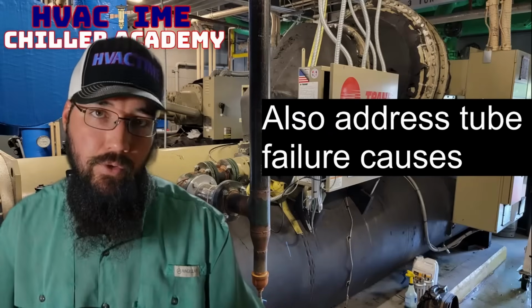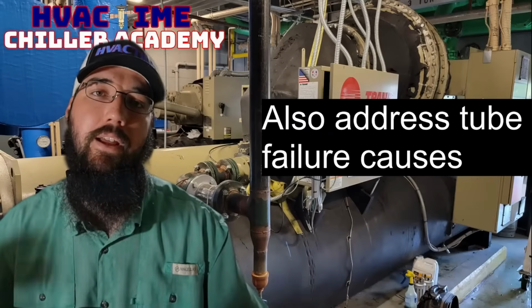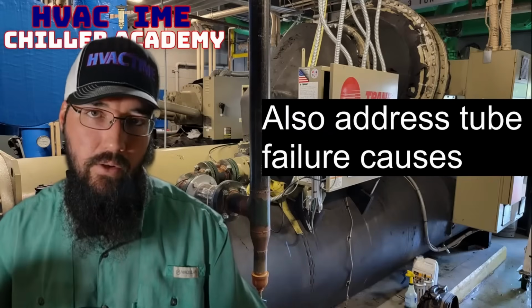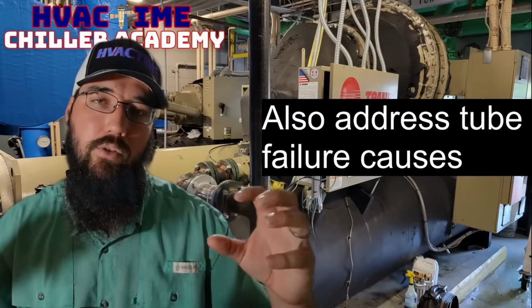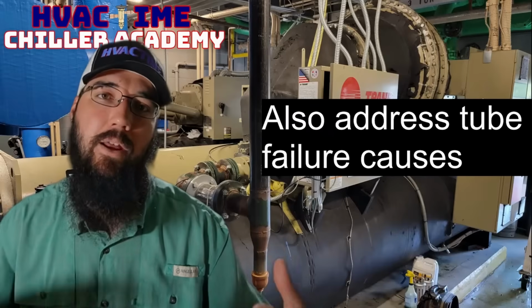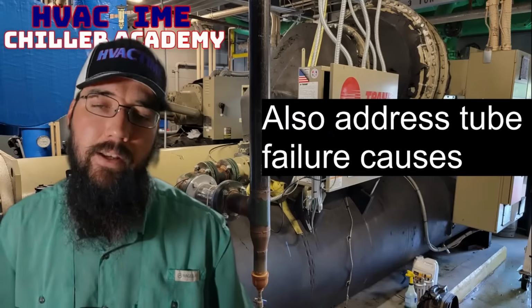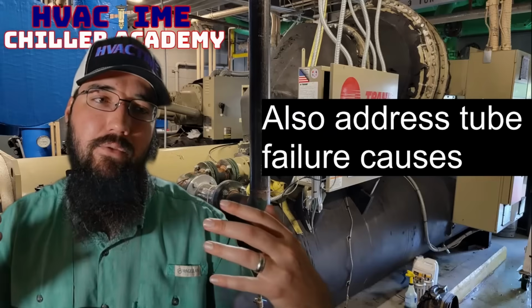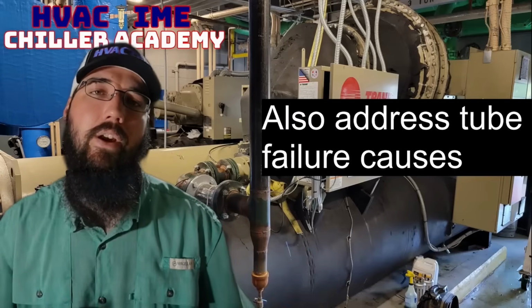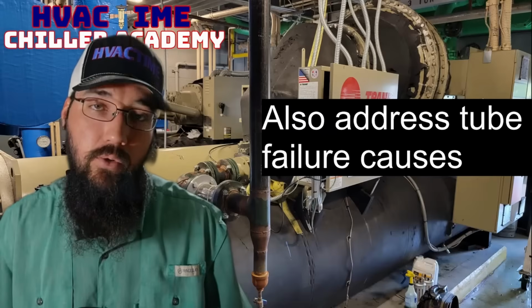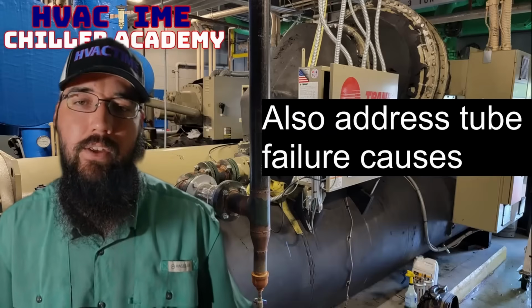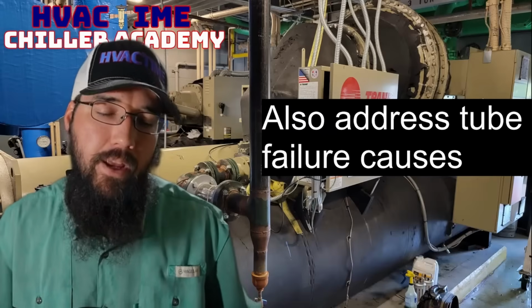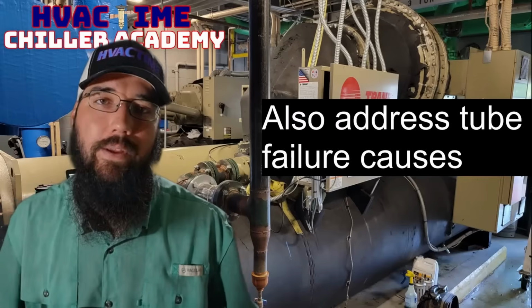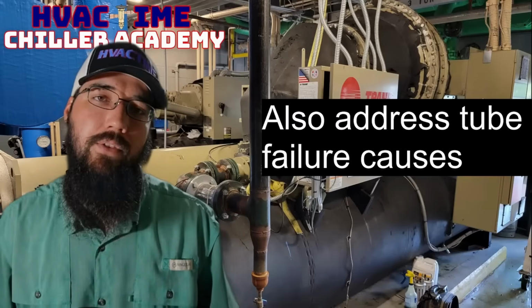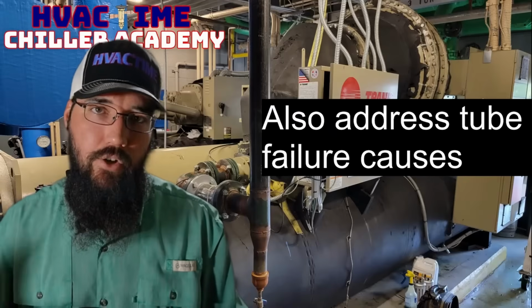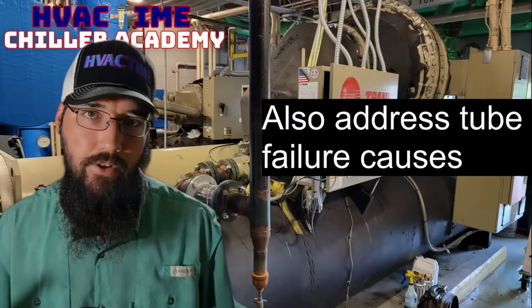More than just the internals of the tube between the two end plates, the actual end plates themselves, where the tube is swedged to the end plate, can also become the leak point. So these are a variety of ways that a tube can fail, or tubes, depending on the circumstances. And depending on the type of failure depends on what we can do. The most common thing to do, ideally you catch it early enough where it's not a catastrophic failure, ideally.